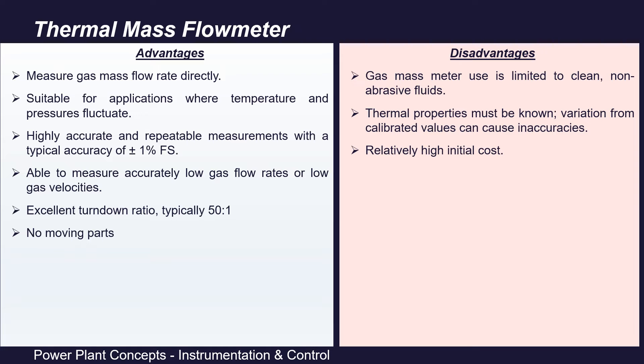Second, it is suitable for applications where temperature and pressure fluctuates. Third, it is highly accurate and repeatable, and we can say it has an accuracy of plus minus 1% of full scale. It can measure accurately low gas flow rates or low gas velocities. Its turndown ratio is very good: 50 is to 1.